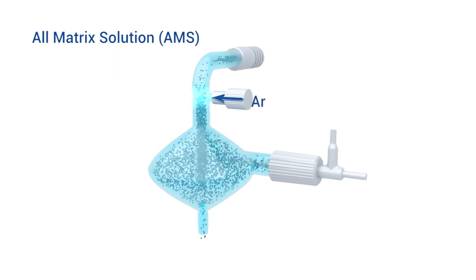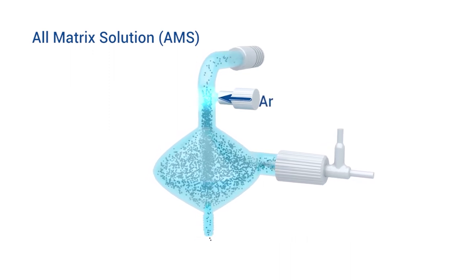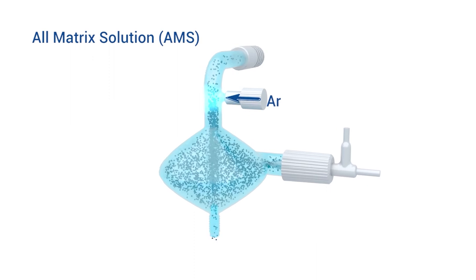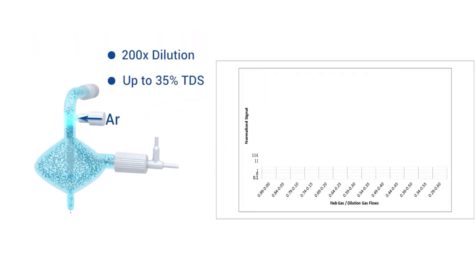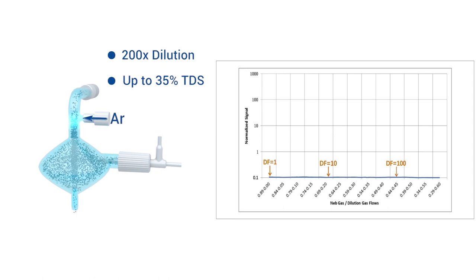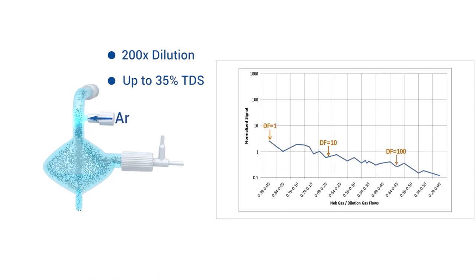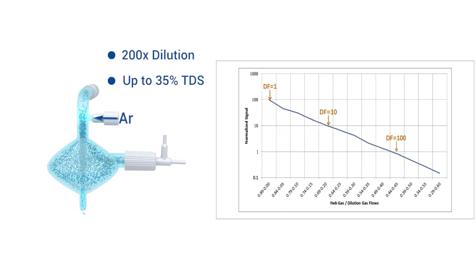Improving efficiency and preventing contamination, it delivers up to 200 times dilution and supports samples even with 35% total dissolved solids without needing to manually dilute.